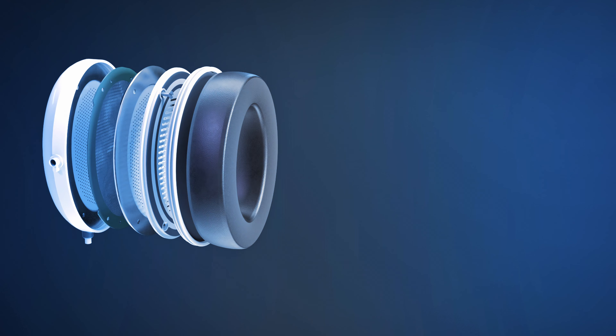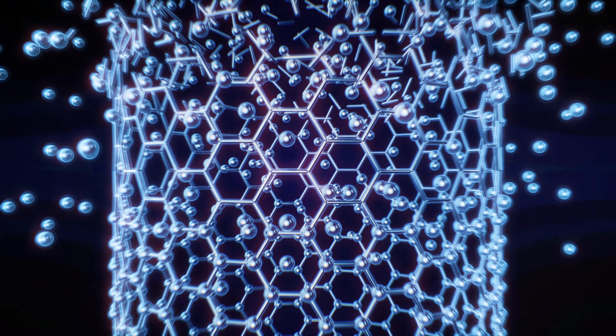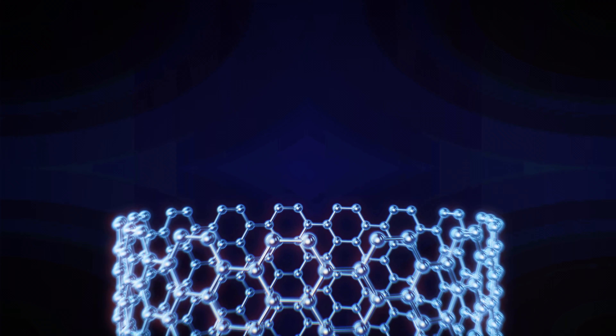We designed this to work with different patients. We did a lot of user testing, so we were able to make the adjustments needed for the design to make sure it works with the most amount of people. When we put the carbon nanotubes inside we basically create some sort of bridges — they touch each other throughout the volume, and we found that single-wall carbon nanotubes work the best. The benefit is we are driving the diaphragm with much more uniform force and there are no issues with reliability of the diaphragm.